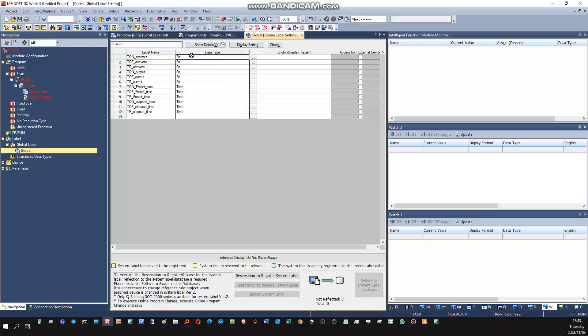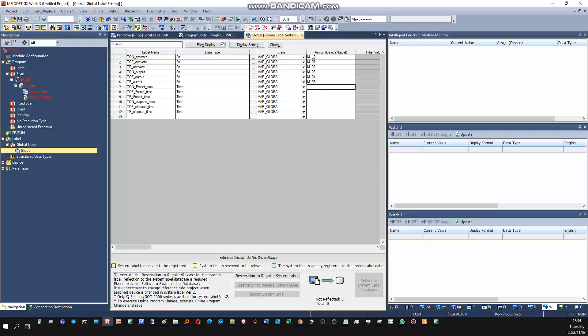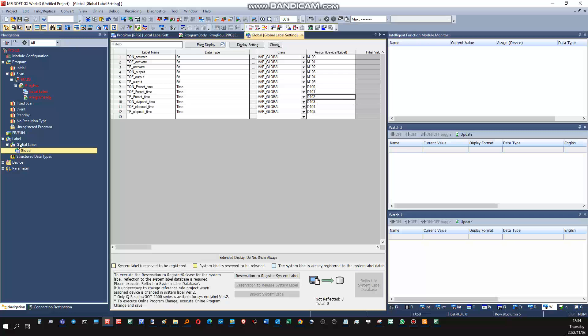Okay, variables are set, but remember we have to output these variables to GOT, so what happens now, we're going to have to display the details and give each one an address. Bits can be inputs, outputs, or M registers, and obviously time will be a 16-bit word D register. I'm going to go M100, M101, M102, M103, M104, M105. They are the six bit variable addresses. And then the D registers: D100, D101, D102, D103, D104, D105.